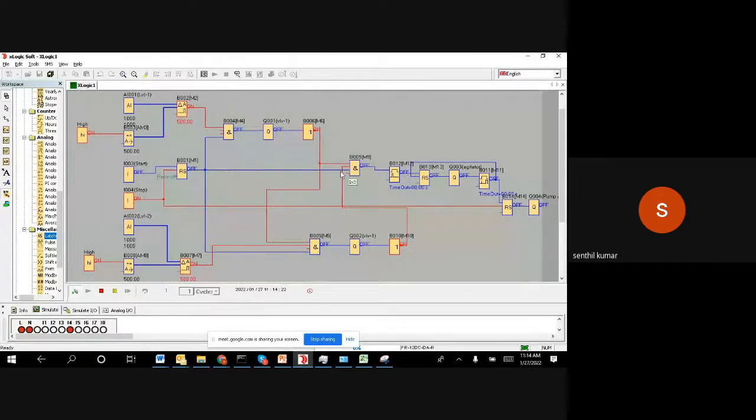See what is happening. Very initially the first valve is closed and the second valve is also closed. After closing these valves, if the system is running, we start the agitator. That's the logic we made actually. So that is making a little trouble. It should not be there. Somehow we need to make sure the logic works correctly here.